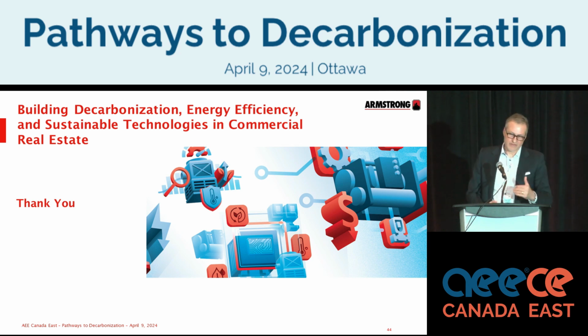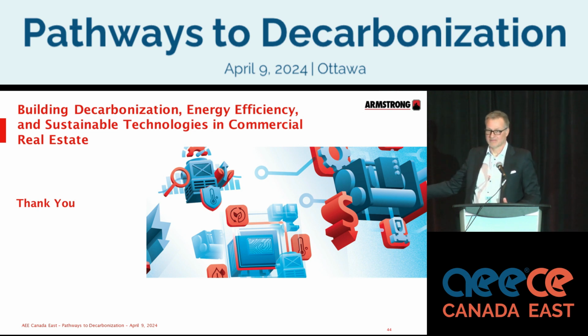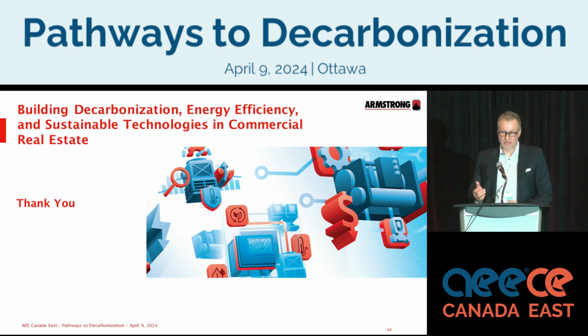The reason I bring in surface area, though, is that now, as we move to low temperature systems, that's going to affect cost greatly. 15 million on fan coils, you know, but there is an ROI associated with it. So that becomes part of the discussion, is like, we have to stop looking at, I'm a pump manufacturer, there's a chiller manufacturer, there's a tower manufacturer, there's my fan coils. It's a system, right? You don't buy a car and have mismatched tires.